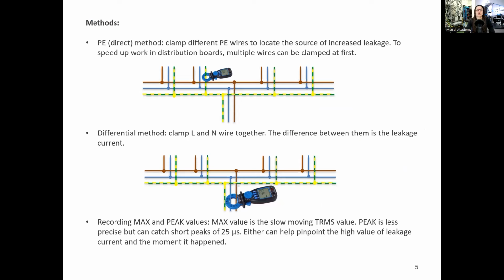Now let's look at the actual measurement methods. We're going to use this simplified schematic of a bus bar in a distribution board. So here at the bottom, we have the main supply connections, and on top, we have connections to different parts of the installation. Now, leakage current, as it flows away from its designated path, generally ends up somewhere in the protective earth wire. So the easiest way to measure it is simply to use the clamp to measure how it flows in the protective earth wire. This method is called the PE or the direct method.